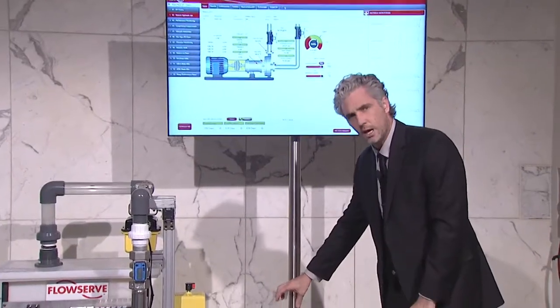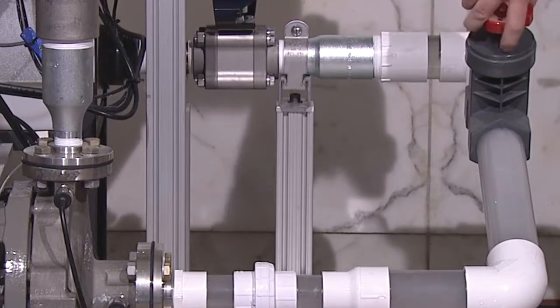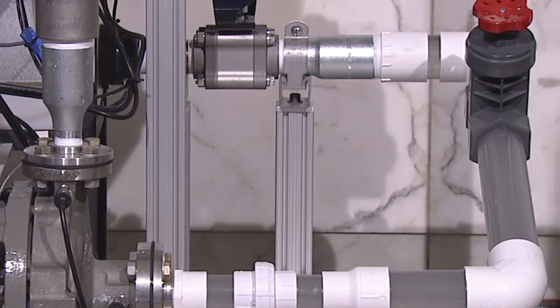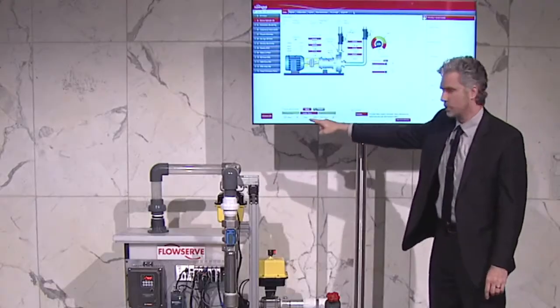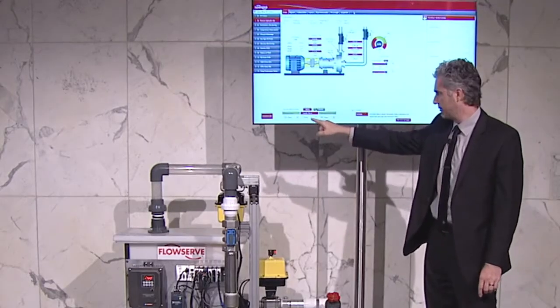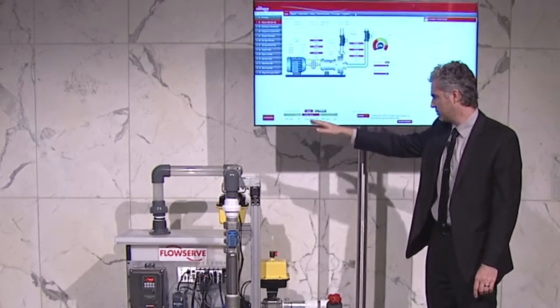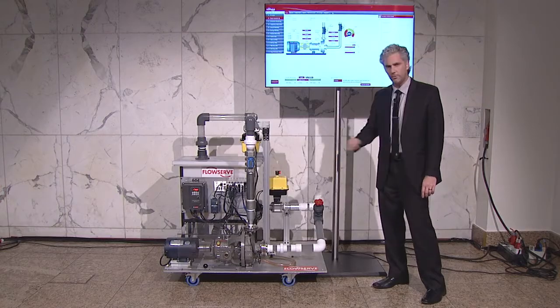I can tighten down this valve. You'll see bubbles start to appear in the inlet line, and it's predicting that in about five days we're going to have an impeller failure in this pump.